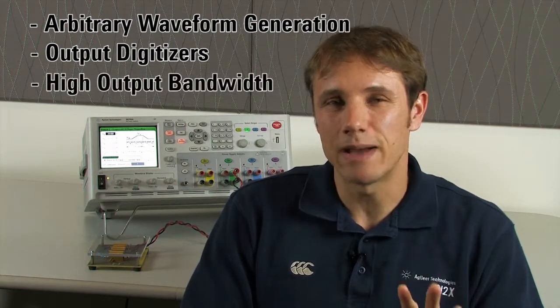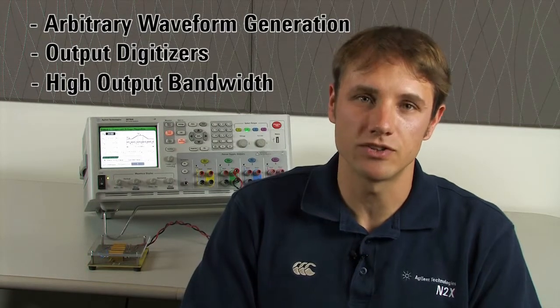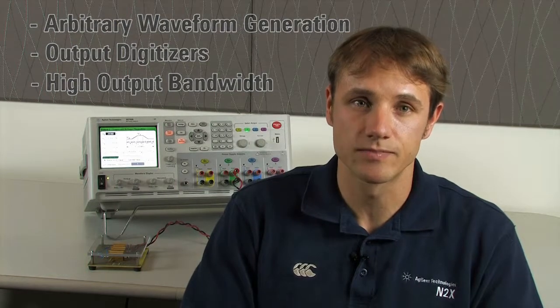The first is it has built-in arbitrary waveform generation capabilities. The second is it has output digitizers for capturing its output voltage and current, so you can see the waveform that was generated. And finally, modern power supplies like the DC Power Analyzer have high output bandwidth compared to power supplies of the past.